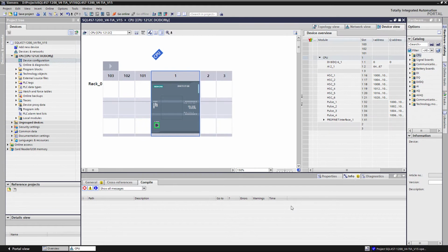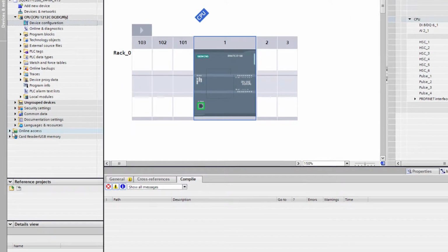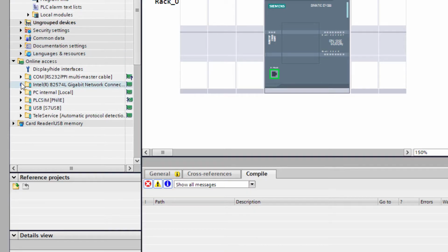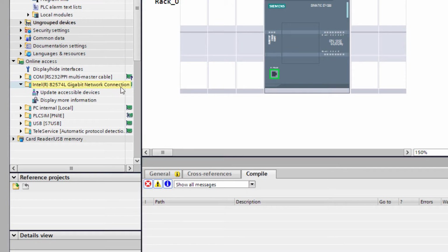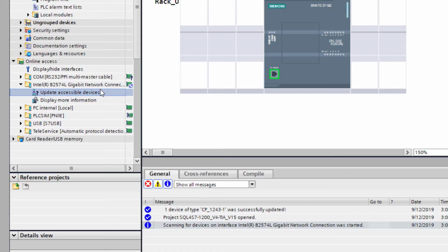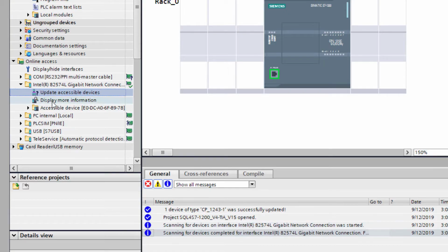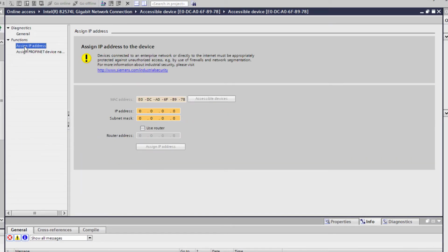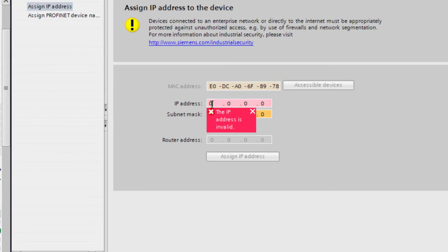Next, I'm going to assign an IP address to my device. There are a few different ways in which you can do this. One way is by going to online access and selecting the network interface for which you are connected to the PLC. Then we double click on update accessible devices. And there we go, here's our PLC. Next, we can double click here, go to functions and assign IP address.